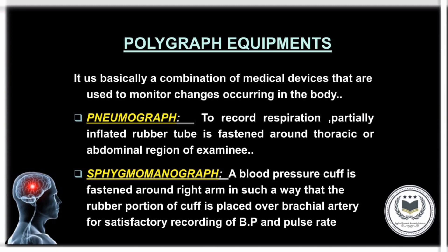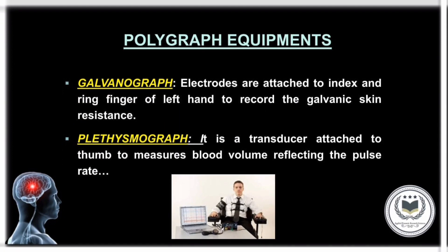Polygraph Equipment: First is the Pneumograph, which is used to record respiration. It is a partially inflated rubber tube fastened around the thoracic or abdominal region of the examinee. Next is the Sphygmomanometer — a cuff fastened around the right arm so that the rubber portion is placed over the brachial artery for satisfactory recording of blood pressure and pulse rate. The third is the Galvanograph, where electrodes are attached to the index and ring finger of the left hand to record galvanic skin resistance. The last is the Plethysmograph, a transducer attached to the thumb that measures blood volume, reflecting pulse rate.